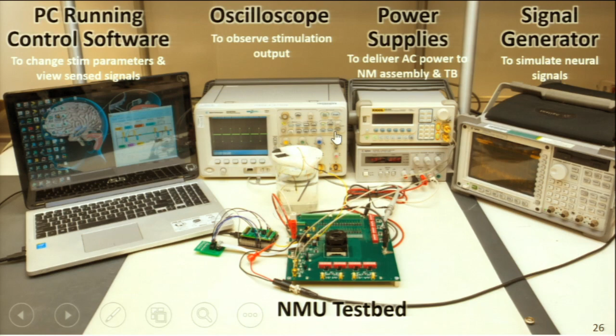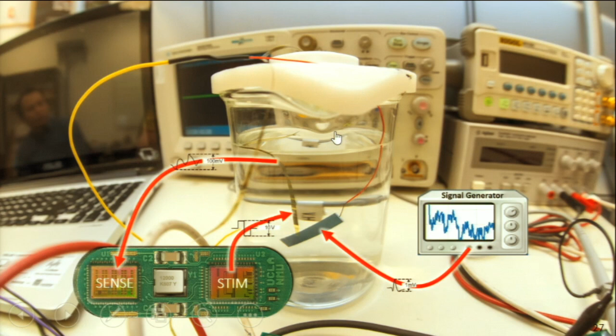And this was done in saline here with electrodes to perform in vitro experiments. And so here is the reference electrode through which we inject the signal. And then on the actual electrode, we do stimulation and sensing. And so you want to see that you would be able to pick up this injected signal on the sensed electrode in presence of a very large stimulation artifact so that you can demonstrate full duplex sensing and stimulation.